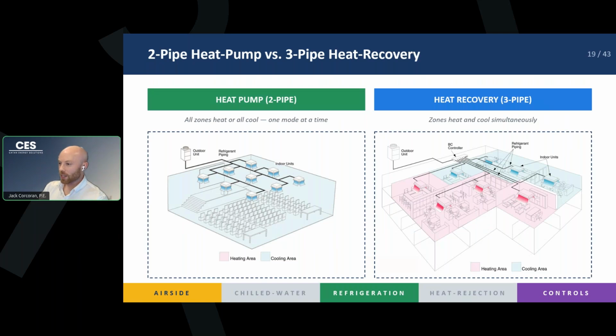I will say there is one manufacturer, Mitsubishi, who has heat recovery with 2 pipes. It has other consequences at our branch boxes. It's just another way of doing it. But for the most part, all manufacturers except for Mitsubishi use 3-pipe heat recovery. They all function the same way, right? But just one has 3 pipes and one has 2 pipes. We'll talk about the 3-pipe configuration here just to keep it easier without the exception.